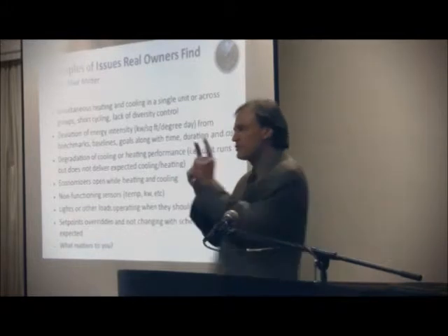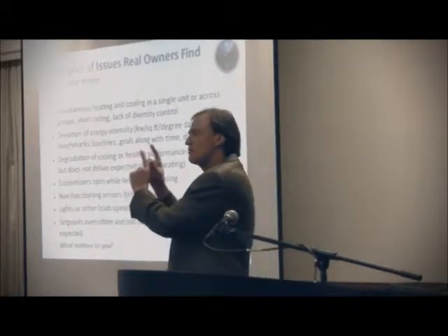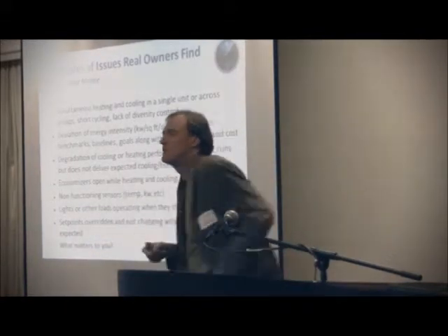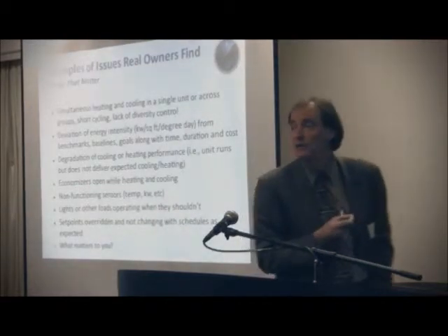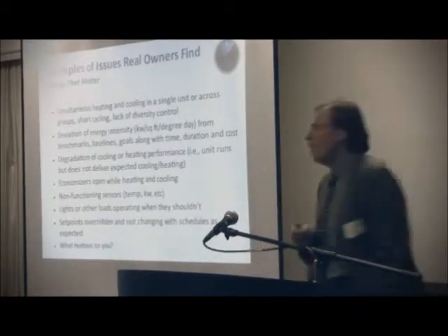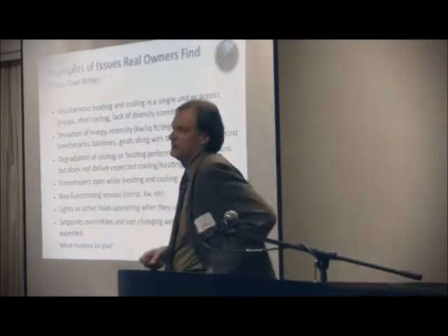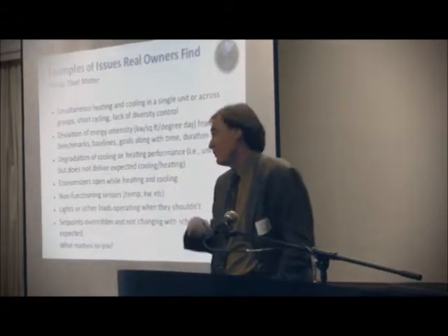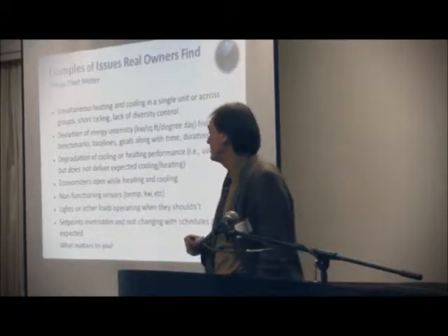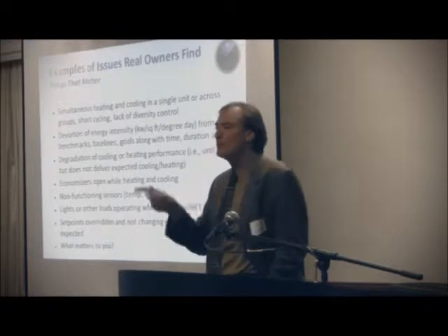Does it happen for short periods—15, 30 minutes at a time, randomly through the day—which might relate to a mechanical problem like a sticking valve? Or does it happen all day, every day, indicating maybe we need to clean the gunk out of the coils? Big difference, but the building's still running.